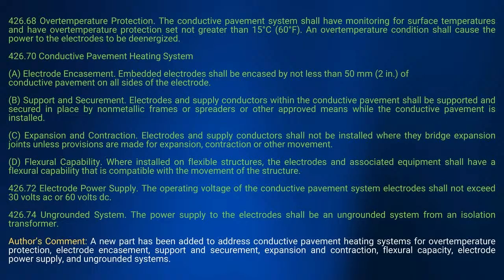They tell you these systems are going to have a monitoring system put in place that monitors the surface temperatures, and also have over temperature protection set not greater than 60 degrees Fahrenheit. This over temperature condition shall cause the power to the electrodes to be de-energized automatically—it's not going to be some GFCI doing this.